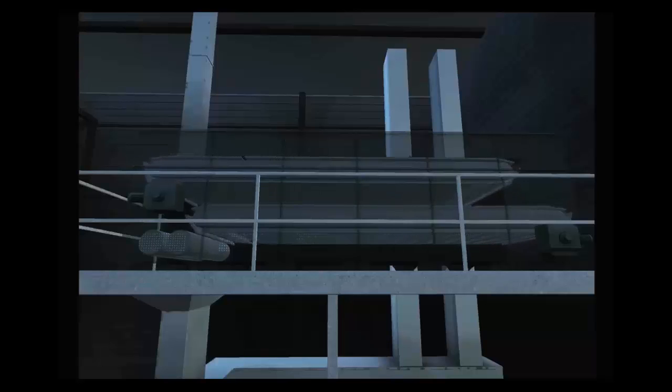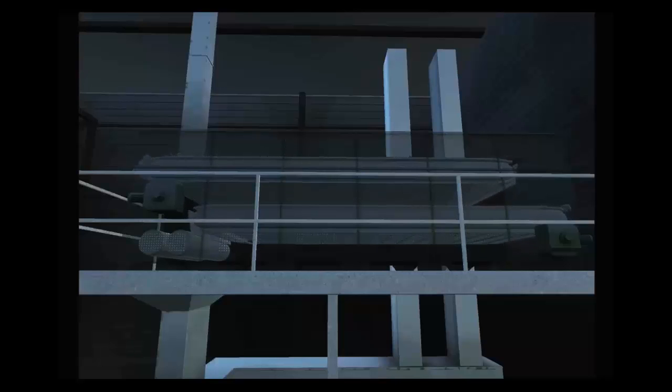The blue area indicates the cooling zone, where the air is also preheated prior to going through the pellets on the top deck, where the majority of the drying should be occurring.